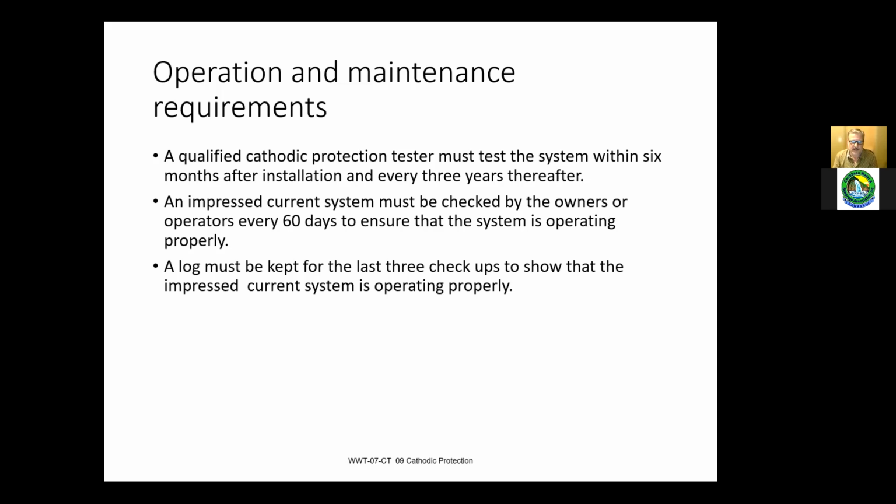Also annually, we have a tester come out and test our whole line. Our discharge line is all steel out into the lake, and it's about 65 meters or so. So you need deep sea diving with hyperbaric chambers to access it. So it definitely is something that's not easy to look at. So we spend a lot of time making sure that it's protected properly.